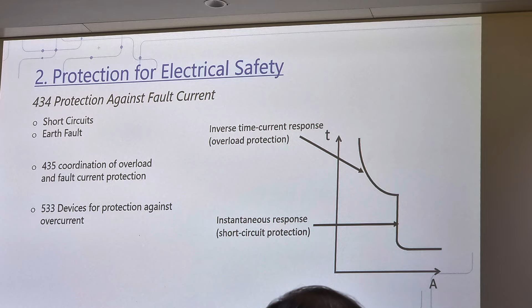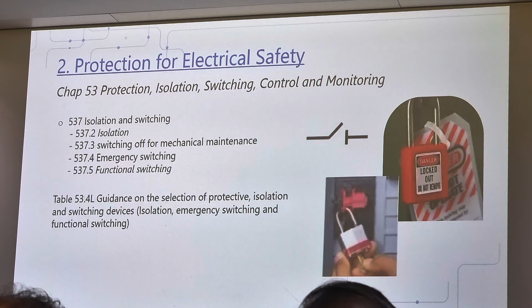Now, the other thing we want to ensure safety is that we have to make sure that the supply is isolated properly. So earlier I talked about the SLD diagram. We want you to show all sources of supply. It could be generator source, it could be from the power grid, it could be from your solar PV. All these sources are important because when we work on any of this equipment, any of this installation, we have to isolate. Isolate means we want to isolate our supply completely so that we can work on the equipment, work on the installations. So we talk about isolation and switching.